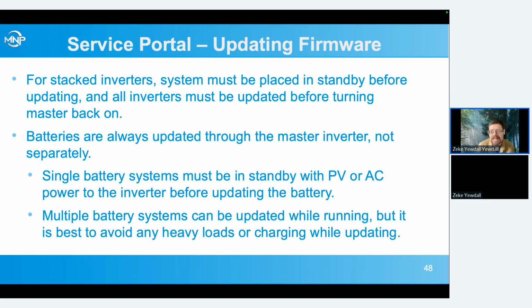For stacked inverters, it has to be placed in standby, and all of the inverters have to be updated before turning the system back on. Batteries are always updated through the master inverter, not separately. If you're using batteries without a Midnite inverter, there is a different procedure for updating the battery firmware with a computer cable connection and special software. But when you're using it with the Midnite inverter, they're just done through the master inverter.